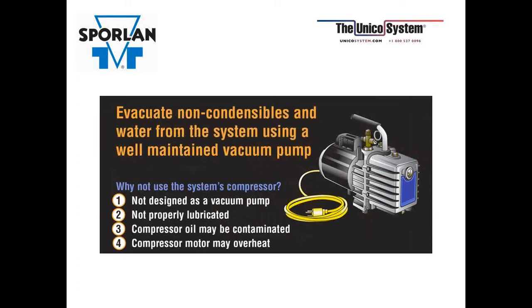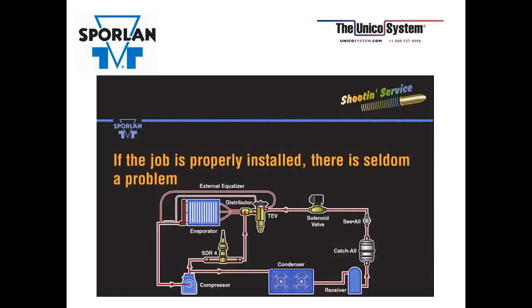Always check with the compressor manufacturer, but most of them will tell you not to use their compressor as a vacuum pump. It's really not designed for that. The compressor valves are not designed to pull a vacuum. It's not always lubricated properly. Compressor oil could be contaminated, which you're going to introduce to the system. And then the compressor motor itself requires cooled vapor across it to cool the motor. So if you don't have any refrigerant in the system, obviously you're not getting that cooling you need. And this is very important too when we get into the I-series with the inverter technology. You've got to pump a deep vacuum.